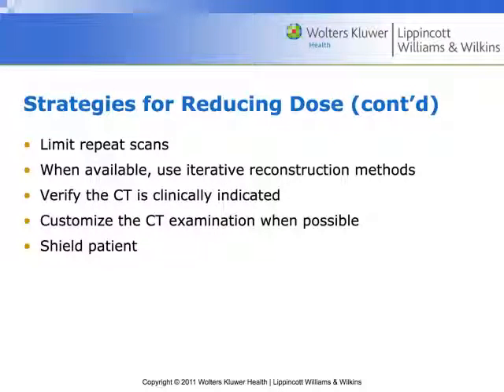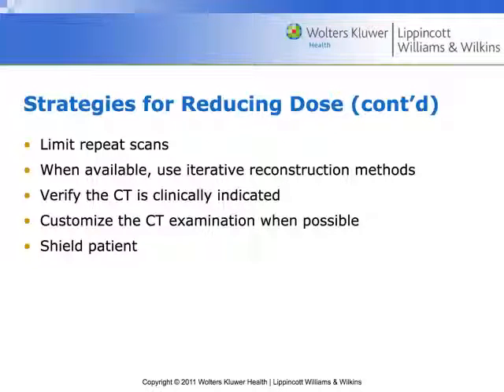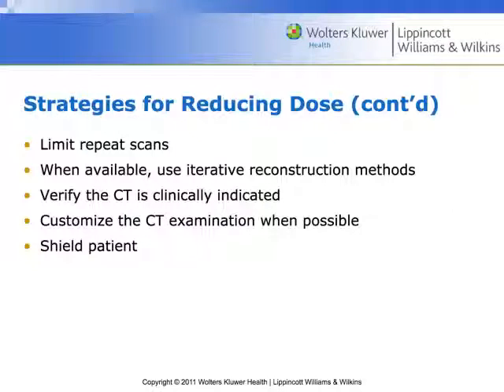We will limit repeat scans as much as possible — one reason we're starting to report CTDI to PACS and EMRs is to track how many CT scans a frequent flyer has had. There are patients who come in repeatedly for chronic pain, and doctors order CT scan after CT scan. Iterative reconstruction methods are important because they allow higher quality images at a lower dose — they untether dose from image quality. Unlike filtered back projection where prettier pictures required higher dose, iterative reconstruction gives better pictures at decreased dose.